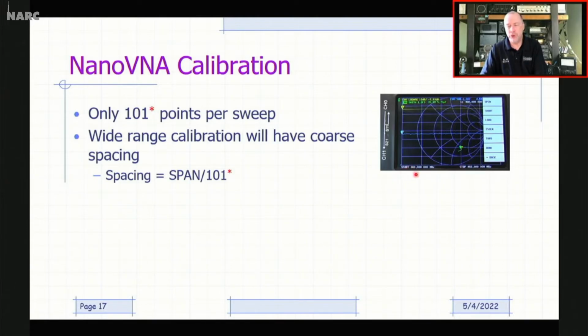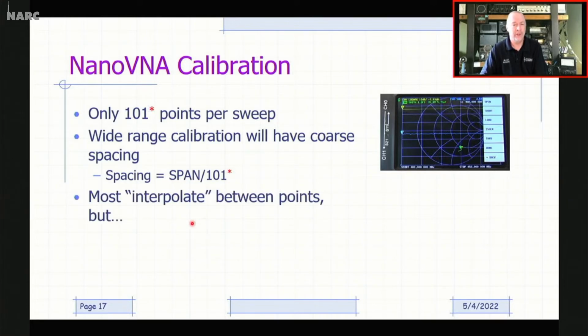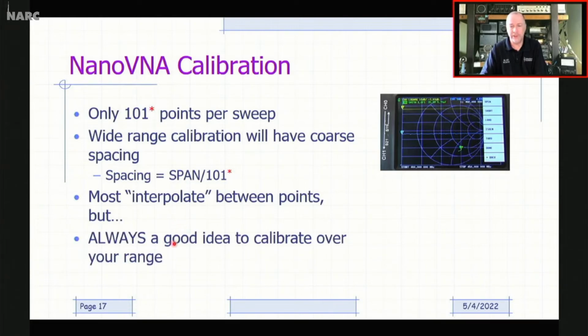Now, if you did a calibration over a wide frequency range, and then reset your measurement frequency range to a narrower range, you may only have a couple of points in that range that are actually calibrated. And the Nano VNA will generally interpolate between those points. Whether that interpolation is valid or not really depends on how wide that spacing is and if you've got any narrowband things going on. So most will do that interpolation, but again, it's always a good idea to calibrate over the specific measurement range that you're measuring in that instance. So it's always a good idea to go do that.